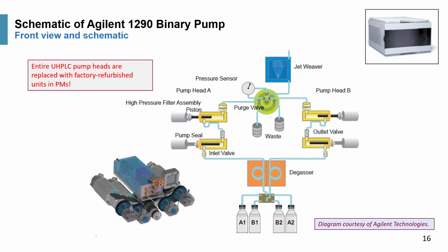Here's a schematic of, once again, a very popular UHPLC, which is the Agilent 1290 binary pump. Showing you the schematic. This is the pump head, and on top of the pumps is the degasser, a 4-channel degasser. Now, the binary pump allows you to mix two solvents at a time, right? Actually, you can have 4 solvents, A1, A2, B1, B2, but you can only mix 2 at a time. But all 4 solvent lines should be filled with solvents.